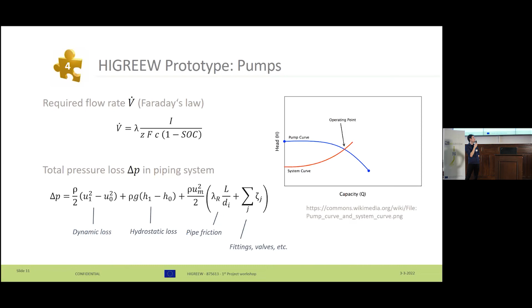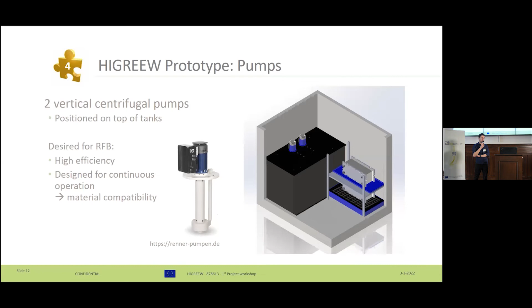And then if you plot the pressure over the flow rate or capacity, you get basically this red system curve. Now when you pick the operating point of your system, you basically just have to pick a pump with a pump curve that intersects the system curve above your operating point. So we chose to go with centrifugal pumps, probably vertical pumps, so again we can save some space in a small container. We put them on top of the tanks. Of course, there are some things you have to consider for flow battery pumps. They have to have high efficiency, and they have to be designed for continuous operation.